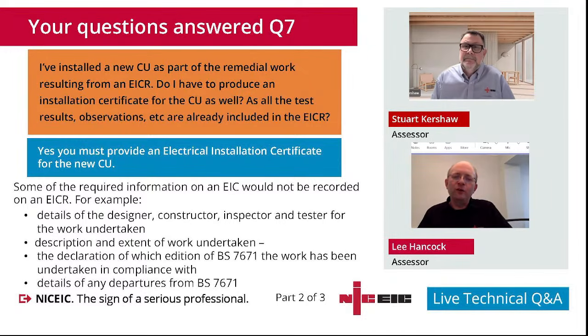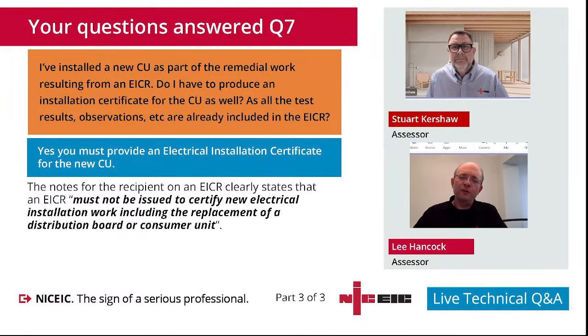Certifying your installation as opposed to reporting it, if that makes sense. You need to issue a certificate to demonstrate compliance with BS 7671. Yeah, and departures, Lee. Departures aren't listed on the EICRs, are they? On the EIC, you state any departures that have been made, if they're applicable. So you're declaring extended liability to what the certificate actually covers, which is just the replacement of the consumer unit.